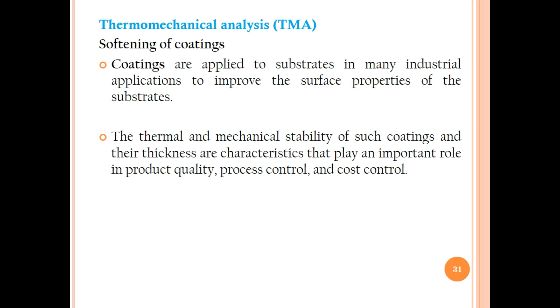In this application, two copper wires A and B with different enamel insulation coatings were measured in TMA penetration mode. The penetration mode and what kind of probe is used have already been discussed. This depends upon the material under observation in TMA. In both cases, the resulting TMA curves exhibit two steps. The first step of each curve, at about 150 degrees Celsius, is due to the softening of the individual insulation coating. At 150 degrees centigrade you can see this first step. Second step, above 200 degrees centigrade, corresponds to decomposition of the coating.